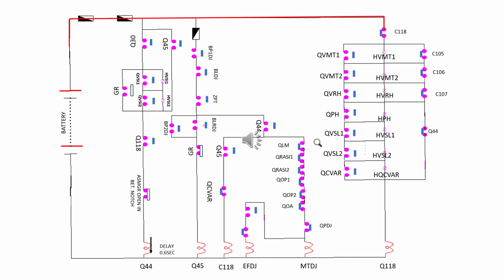Now see the last branch, Q118. It will energize because the C118, C105, C106, C107 and Q44 relays are normally closed contact relays. That means when they are not energized, these contacts will be in closed condition. So the DC positive will come through this path to energize Q118. Q118 gets its positive from the positive side and the negative is permanently connected, so it will be energized. First it will energize Q118.